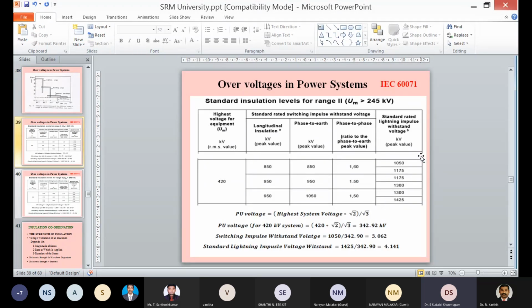I just give this for reference. Let us go for the actual calculation again. Since switching impulse comes under more than 245 kV, I have shown 420 kV. For a 420 kV system, for the time being, I will explain only phase to earth and standard lightning impulse voltage. This is nothing but the standard rated switching impulse voltage. It is short form called SIL, switching impulse level. And this is standard lightning impulse voltage, that is nothing but LIL, lightning impulse level. So what it says is, for a 420 kV system, that is a 400 kV system, highest system voltage is 420 kV. Phase to earth insulation should be tested for 1050 kV and lightning level should be tested for 1425 kV. How they are defined? Let us see.